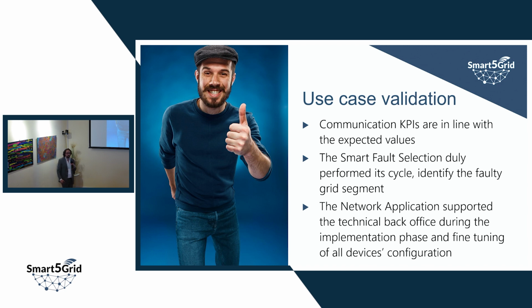The Smart Fault Selection was performing according to expectation, and a special mention to the network application, because we were not only using it during the execution of the test, but also during the implementation of all the field devices, to check if the antenna was positioned correctly, why communication wasn't working, to check the firewall configuration, and a series of steps usually performed while implementing remote control and automation on field. The operative team has been supported in day-by-day operation by this network application, and the feedback from them has been really positive.